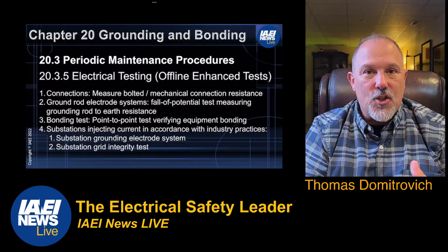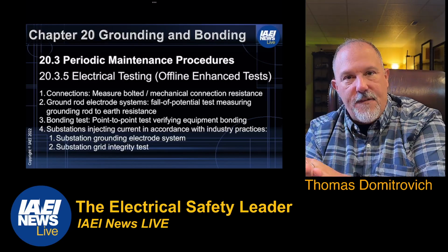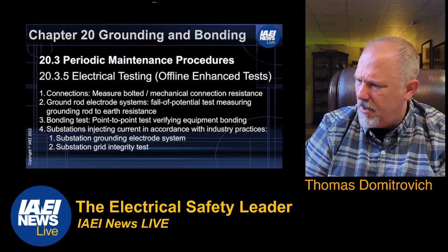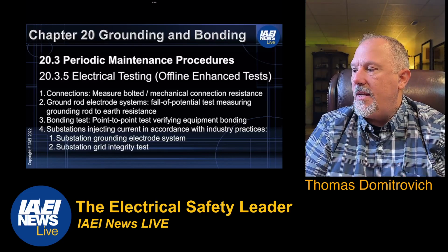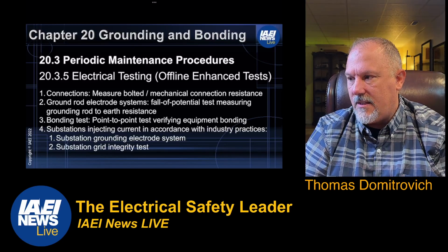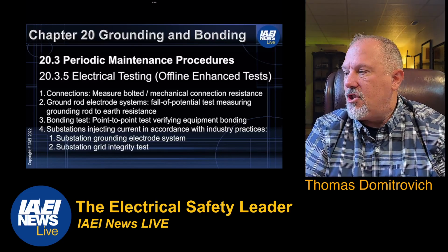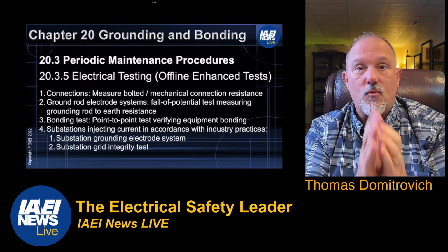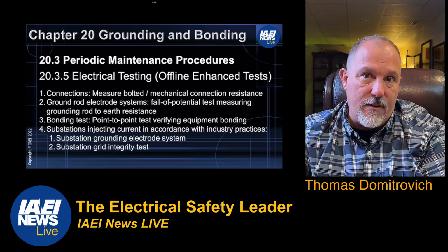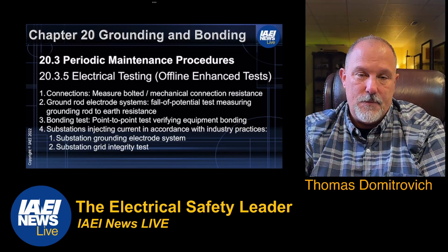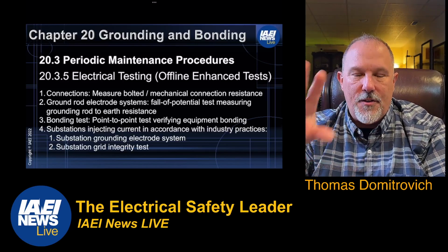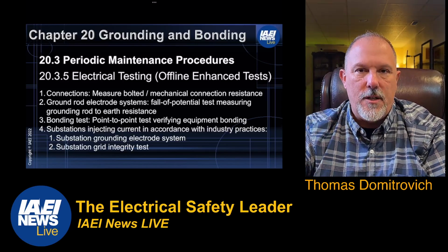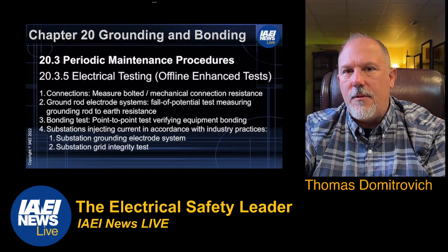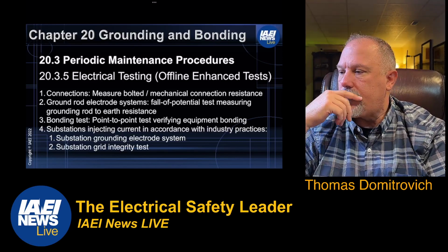20.3.5, the electrical testing. Now, you're going to have offline and online, I believe. This is offline enhanced tests, your connections. Measure bolted mechanical connection resistance. Remember, you're going to do thermography. That's a baseline. Thermography is going to help you determine whether or not there's current flowing through that termination, etcetera.